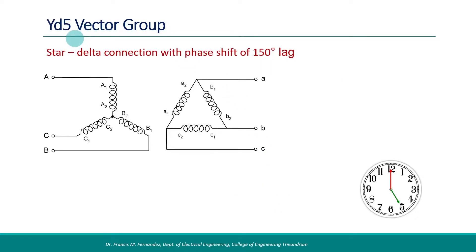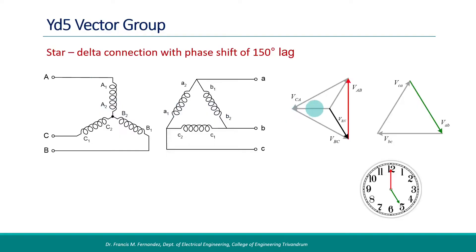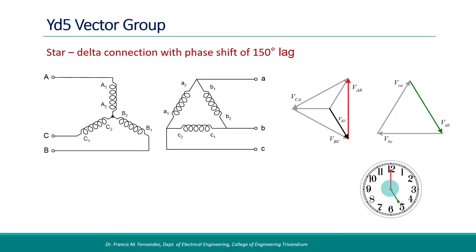Next we consider the YD5 vector group. The primary is star connected and the secondary is delta connected. In the phasor diagram, line voltages on the star connected primary side are decomposed into corresponding phase voltages. Since we are taking line voltage VAB as primary side reference, we need to take VAB for the secondary side also. Here VAB actually comes from winding B of the secondary, and the voltage induced in it will be in phase with the phase voltage of winding B of the primary. The secondary line voltage is lagging by 150 degrees from the corresponding primary voltage — the 5 o'clock position represents this condition. The simplified connection diagram and the displacement diagram are shown.